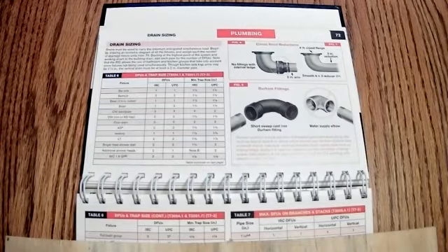Now the bathtub, according to drainage fixture units, is going to be 2, and again, both for the UPC and the IRC. And the trap size is going to be, again, 1.5 inches. Remember, we're going to have a trap on there, trap and drain size.